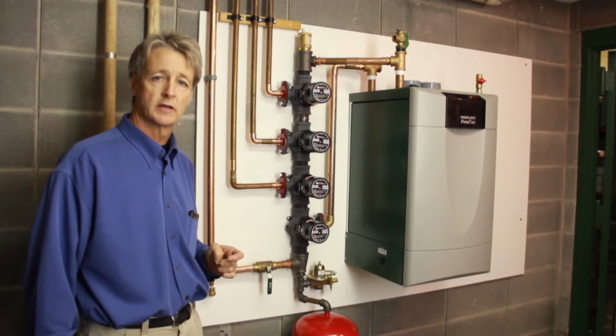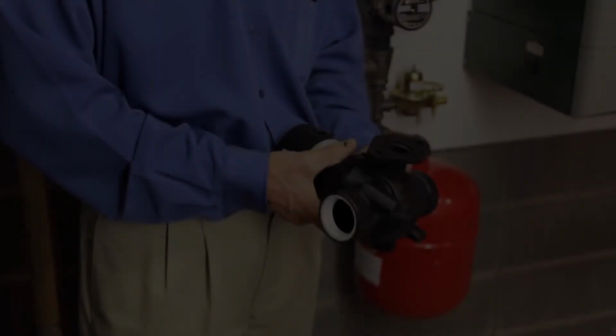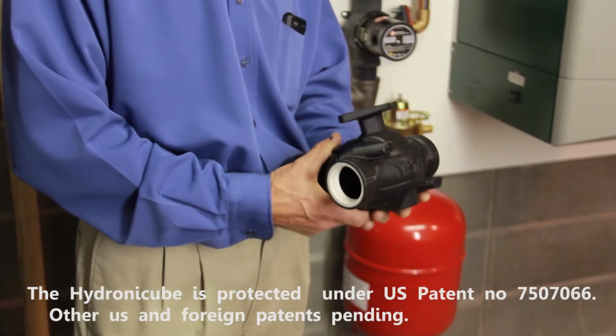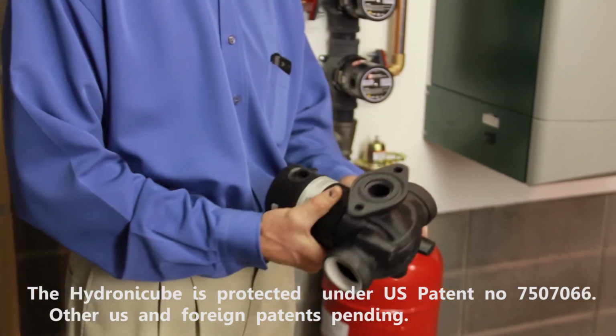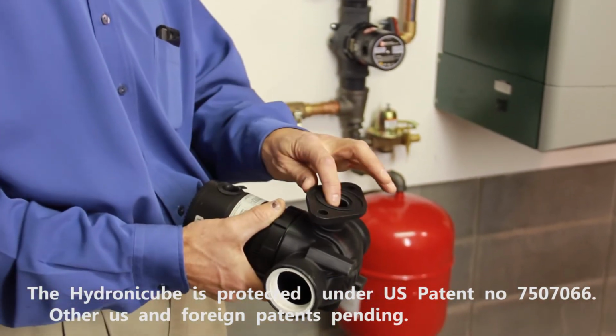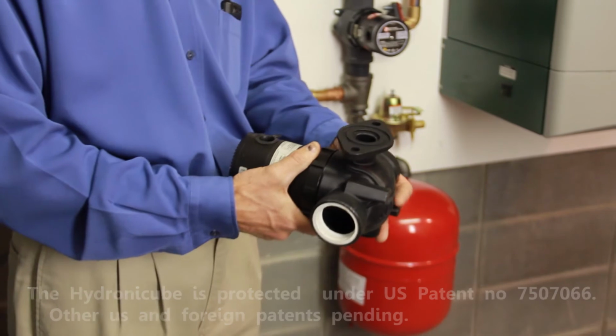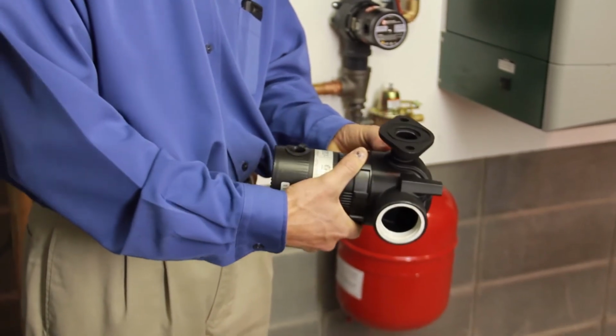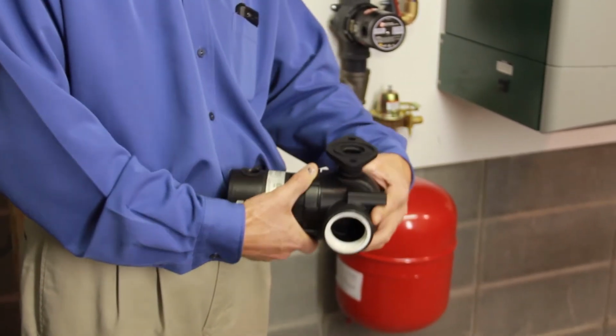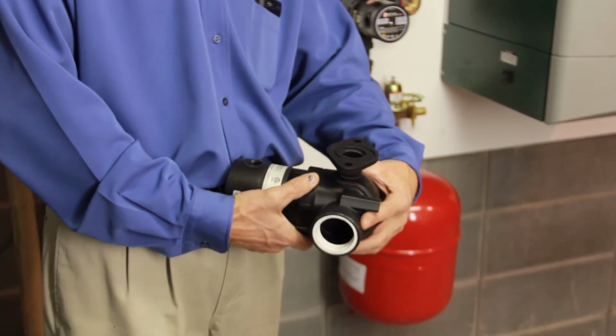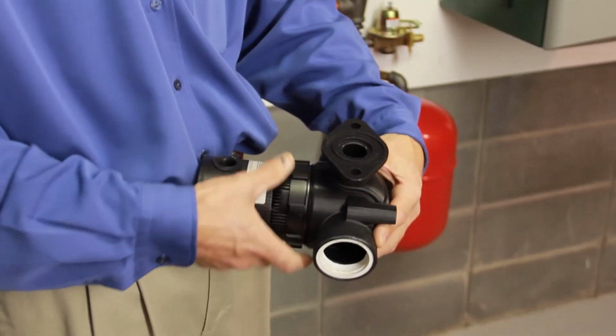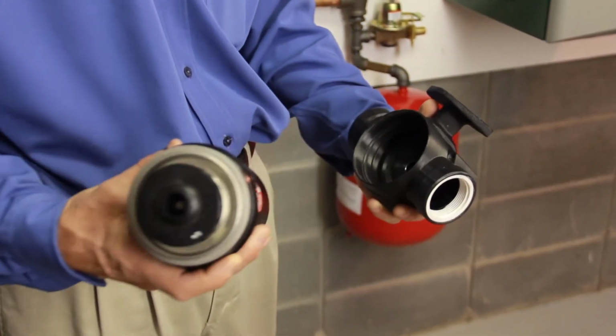Let's take a closer look at the Hydronicube body. The patented Hydronicube body is unique in the sense that it has two inlets and one outlet. The motor and pump assembly is held onto the cast iron body with a screw ring. To remove the pump, you simply rotate the screw ring counterclockwise and detach the pump.